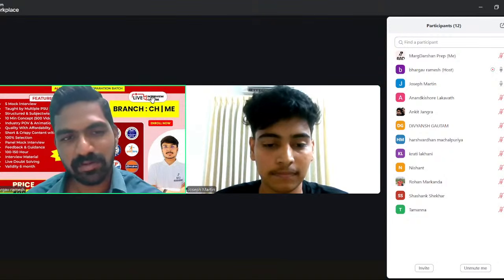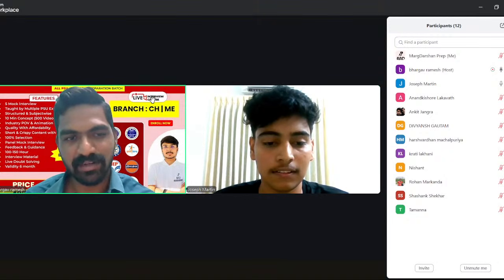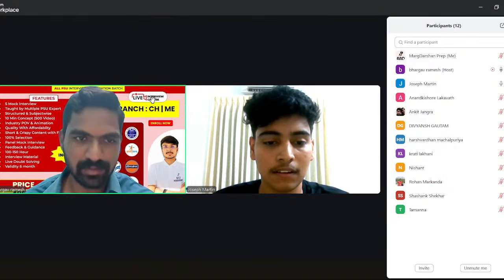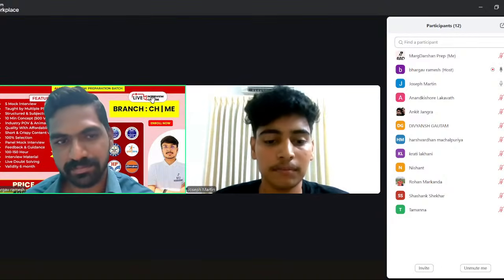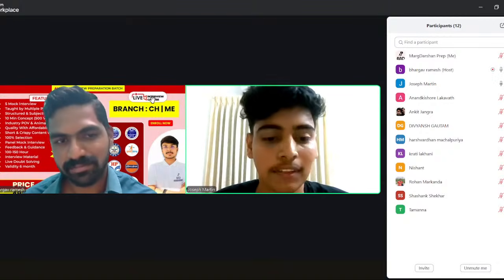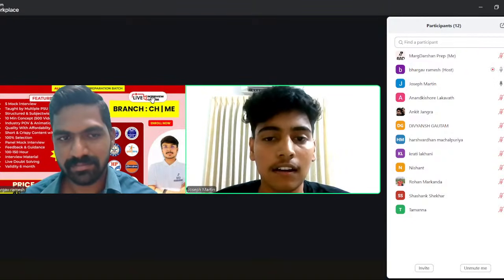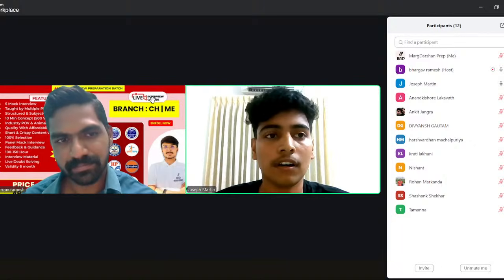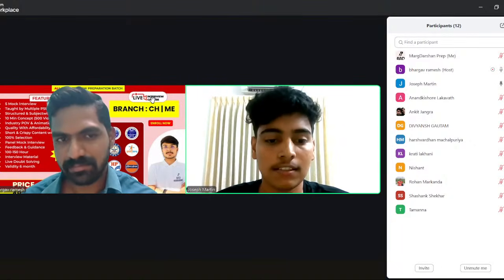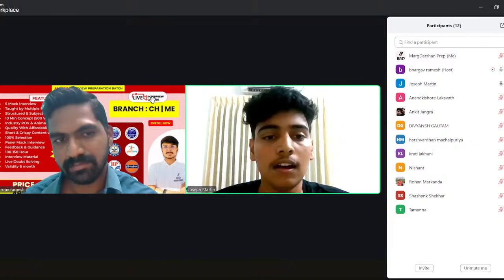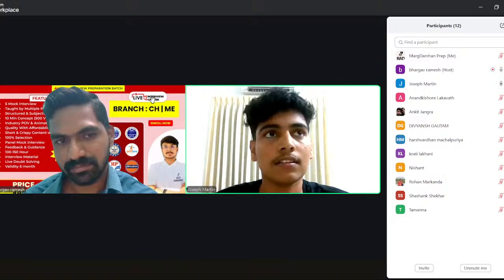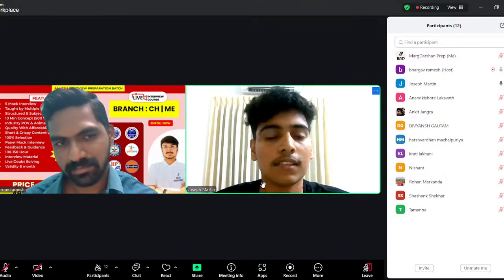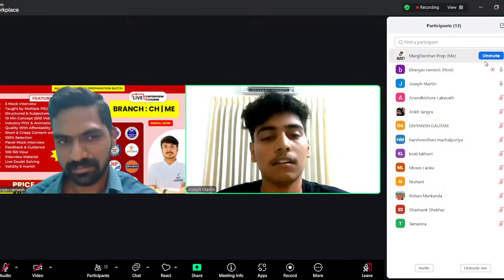Okay, Joseph, what did you observe? What is the difference between your first day and second day, looking at the 400 kV switchyard and the 220 kV switchyard? What is the main difference that you observe? The size was larger compared to 220 kV. For 400 kV there were 2 feeders. We also had 10 units of transformer, 3 each for 3 phase. It was an auto transformer, and for 220 kV, I think there was one single 3-phase unit as well as 3 single-phase units.